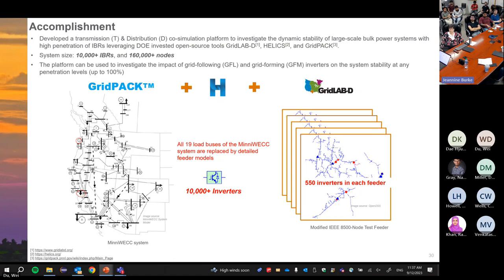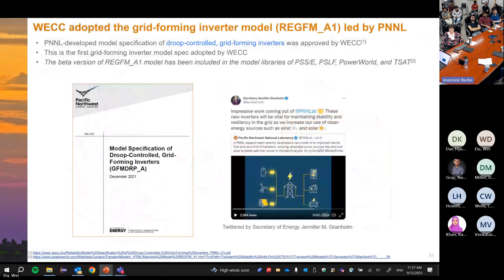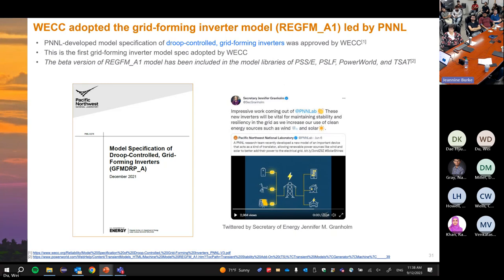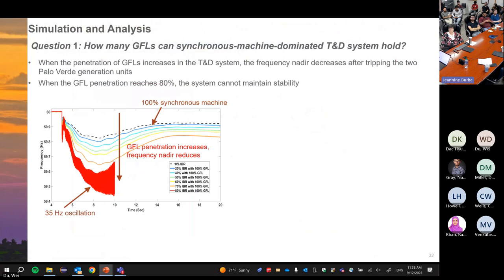For the simulation platform, we need grid-forming inverter models. I've been working heavily with industry, including WECC and software vendors, developing inverter models to help utilities understand how grid-forming inverters impact the system. This is a WECC-approved grid-forming inverter model specification developed by PNNL — the first WECC-approved grid-forming inverter model and the first time WECC adopted a model specification developed by a National Lab. This work was quoted by the Secretary of Energy on Twitter. Basically it's a simple droop-controlled grid-forming inverter model used to evaluate system response.